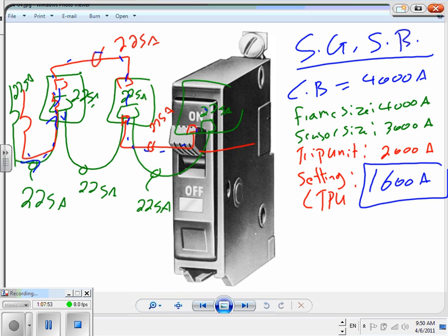See how when you go into the power circuit breakers, every circuit breaker actually has 4 settings for the same circuit breaker, when you count the plug-in unit. Here's the physical mechanical frame. Here's the CT, the physical frame. This is the trip unit that you can plug in and change. And this is the actual circuit breaker.